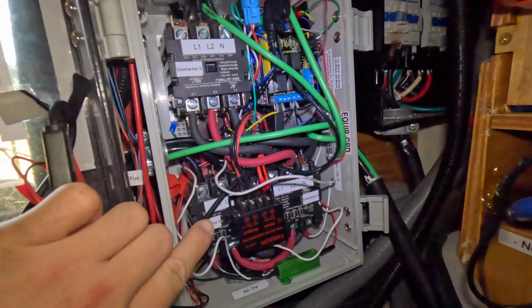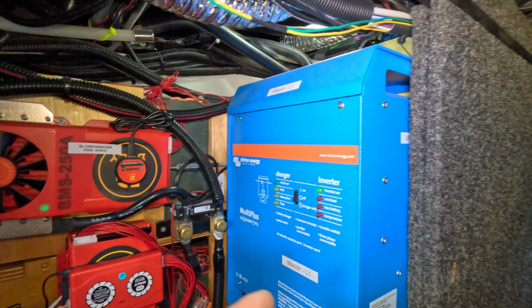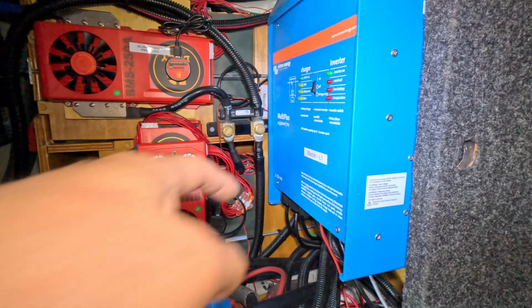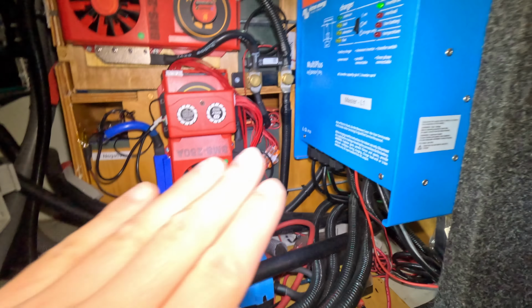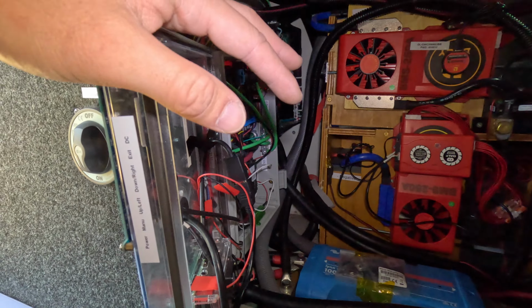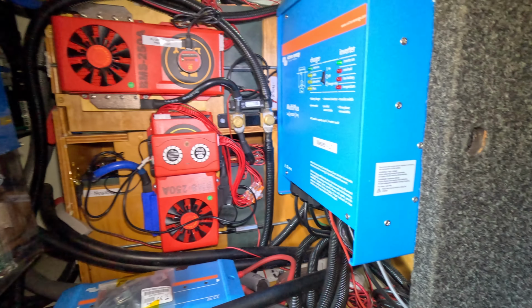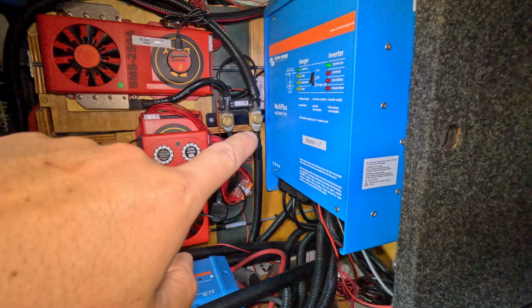Boom, we've got 120/240 volt voltage again from here, and then from this side it feeds to two of those multipluses. So essentially, for those two multipluses, they always see 120/240 voltage, no matter what voltage I have inputting - either it's a true 50 amp 240 shore power, or it's a 120 generator, or it's a 120 regular household plug, the multipluses always see 120/240 voltage. And then coming out from those two inverters goes to the inside power distribution panels that I'll show you in a little bit.